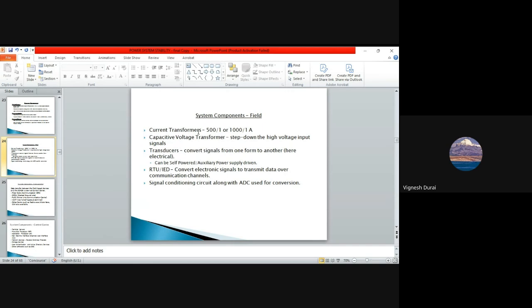Your current transformer will convert. You know what current transformer application is: higher current to lower current, it will convert. Voltage also, same thing: step down the high voltage input to signal voltage. Next, transducers convert signals from one form to another form.